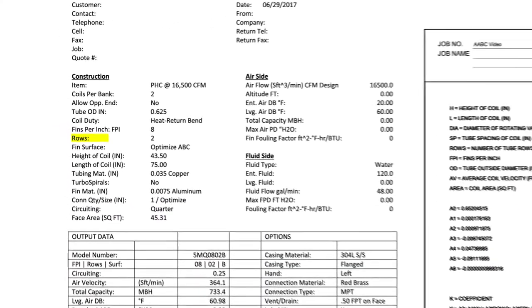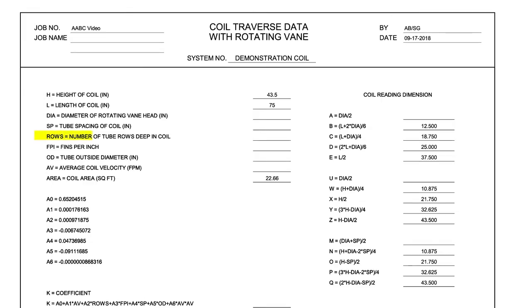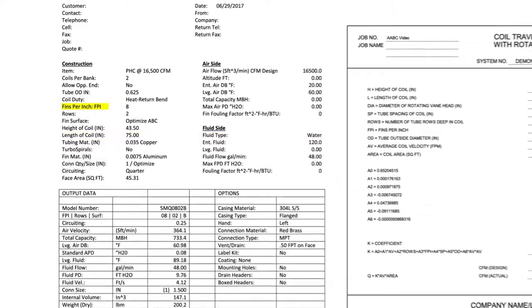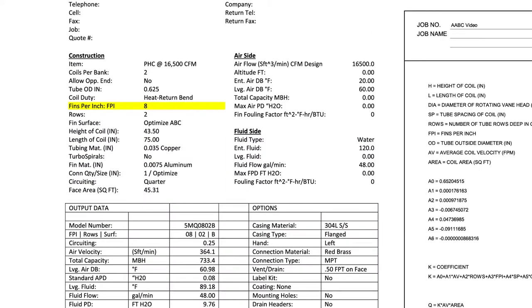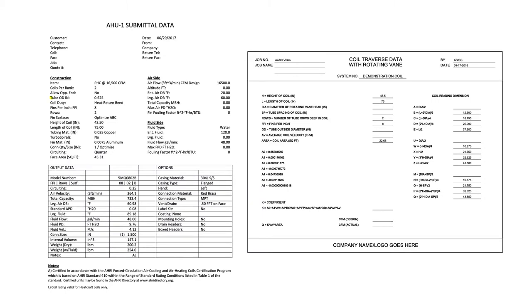From the submittal data, record the number of tube rows deep in the coil: rows equals number of tube rows deep in the coil as two. From the submittal data, record the number of fins per inch: FPI equals fins per inch as eight. From the submittal data, record the coil's tube outside diameter: OD equals tube outside diameter as 0.625.